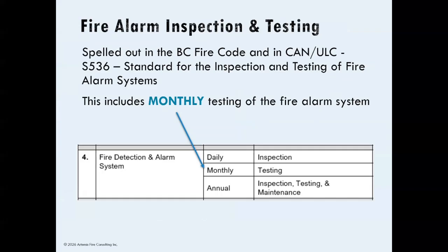Most folks don't realize the full scope of required testing, inspection, and maintenance. For example, your fire alarm system requires not just annual inspections, but also monthly testing as well as daily inspections. This is all included in the CAN/ULC-S536 standard for the inspection and testing of fire alarm systems, which is referenced by the BC Building Code.